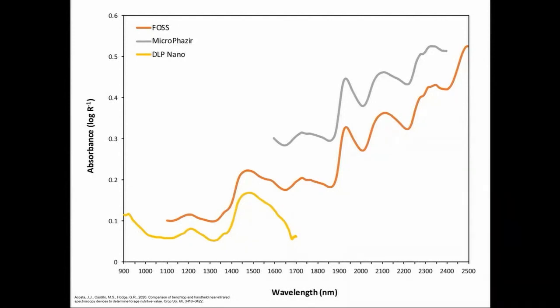And here they compare our log 1 over reflectance, or absorbance, spectrum for the FOSS instrument, the tried and true instrument that's in orange here in the middle, and two low-cost devices. One is an NIRS instrument based on digital light processing, which is a MEMS device, and the other is an NIRS device called the microPHAZIR, again another compact device. But you can see here what we were just talking about, the wavelength range is more limited in the smaller instruments, and that has a lot to do with the instrument design and the detector itself.